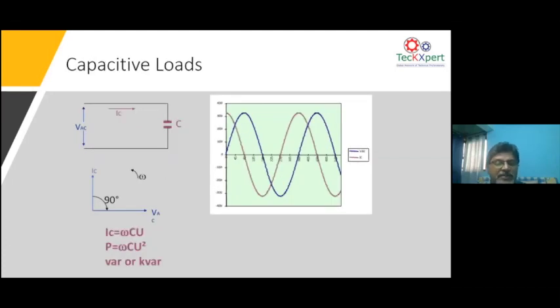Similarly, when it comes to capacitance, as you know, capacitance is inversely related, unlike resistance and inductance. When you take the equation, the current drawn by a capacitor is omega into capacitance into voltage applied. Similarly, the power equation becomes kVAr equals omega, that is 2 pi f, into capacitance into the square of the voltage. So if you have a capacitor of 25 kVAr or 50 kVAr and want to find out the capacitance value, it is simple: 25 kVAr divided by 2 pi f and the voltage, if it is a 440 volt capacitor, and you can easily calculate the C value of the capacitor.